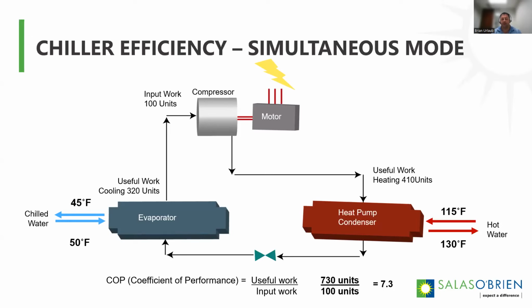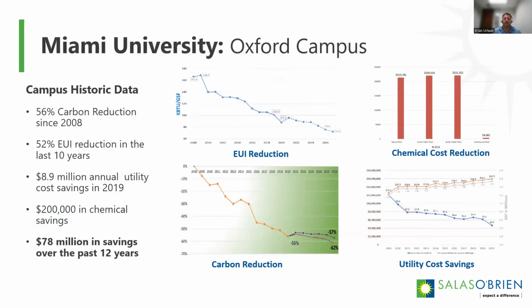In previous systems, what they had before was they had to run a boiler to heat the domestic hot water, and you're running your chiller and your cooling tower to make chilled water. So now we can do that all with one system and really increase the efficiency. So that simultaneous load and figuring all that out in your thermal profiles is extremely important with these district systems to really increase your efficiencies and your savings. So here's a little bit of the metrics with Miami University.